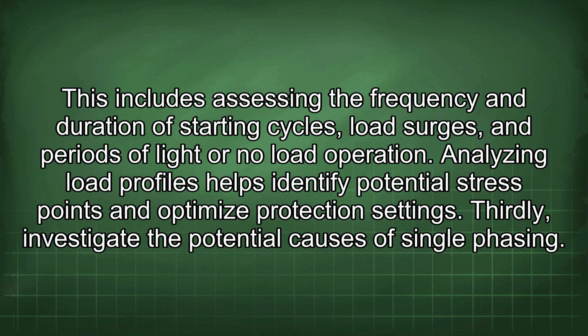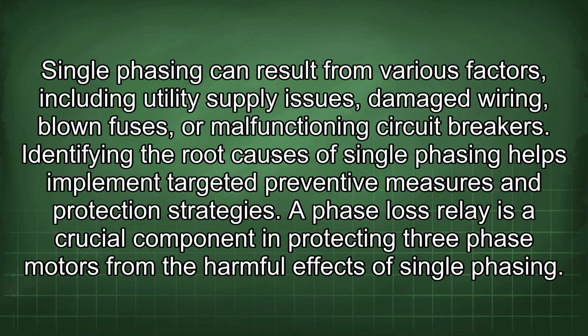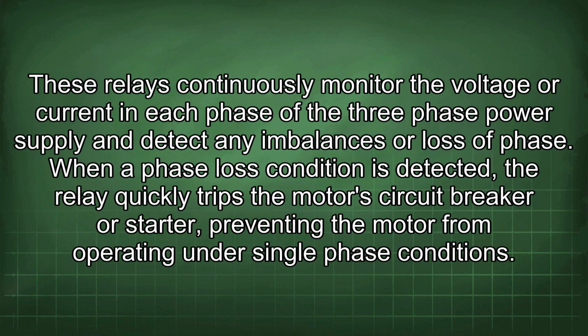Thirdly, investigate the potential causes of single phasing. Single phasing can result from various factors, including utility supply issues, damaged wiring, blown fuses, or malfunctioning circuit breakers. Identifying the root causes of single phasing helps implement targeted preventive measures and protection strategies. A phase loss relay is a crucial component in protecting three-phase motors from the harmful effects of single phasing. These relays continuously monitor the voltage or current in each phase of the three-phase power supply and detect any imbalances or loss of phase. When a phase loss condition is detected, the relay quickly trips the motor's circuit breaker or starter, preventing the motor from operating under single-phase conditions.